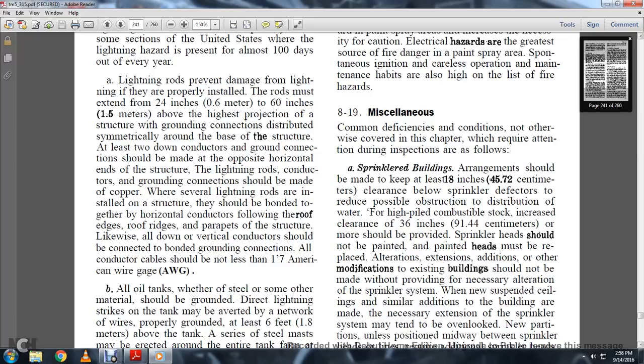Sprinkler buildings: storage arrangements should be kept at least 18 inches clear below the sprinkler deflectors to reduce possible obstruction of the distribution of water. For high-piled combustible stock, an increased clearance of 36 inches or more should be provided. The sprinkler heads should not be painted. Painted heads must be replaced.